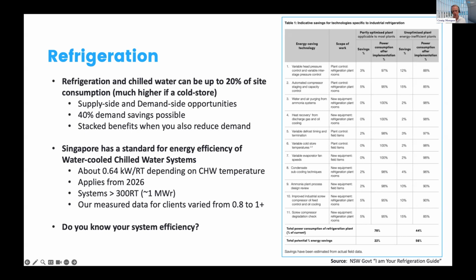They put floating head pressure control, 30% measured and verified reductions out of that system happened once the project was done. And that's 20 years ago. And there's still many, many systems around that don't have that capability. And also things change as well, right? So we know that production on a lot of sites changes. And so what that means is low-hanging fruit does regrow. You would have heard that saying before, because the load profile of things change, which means that the system you have may not be as adaptable or as efficient in delivering that particular load.